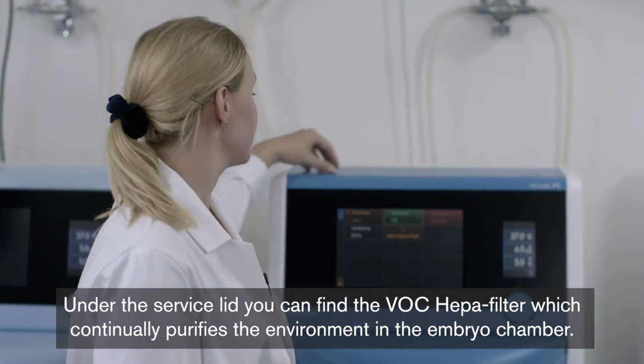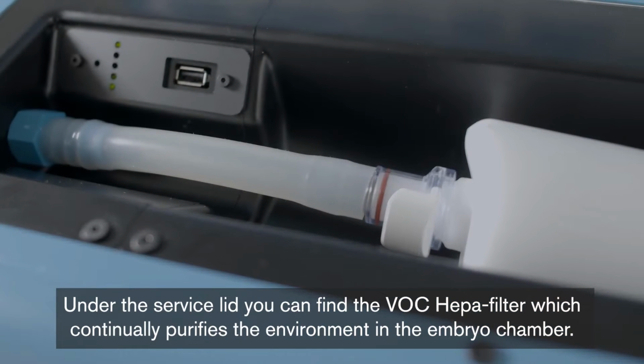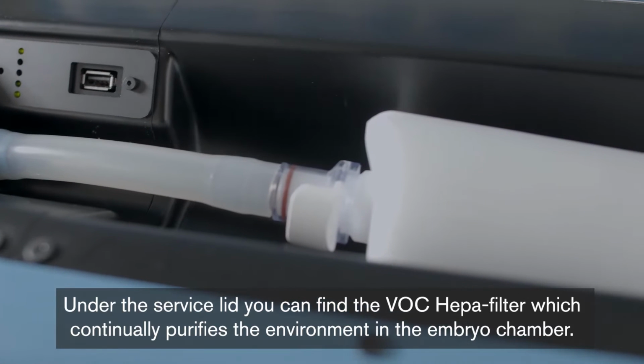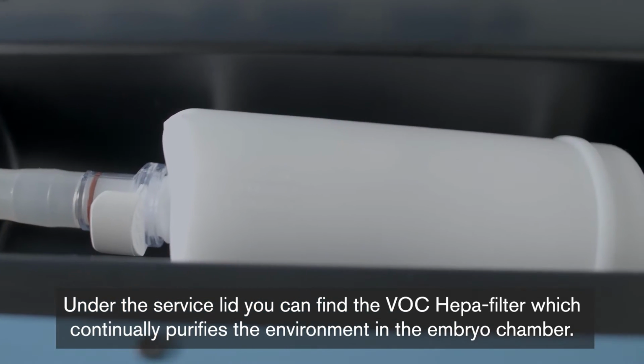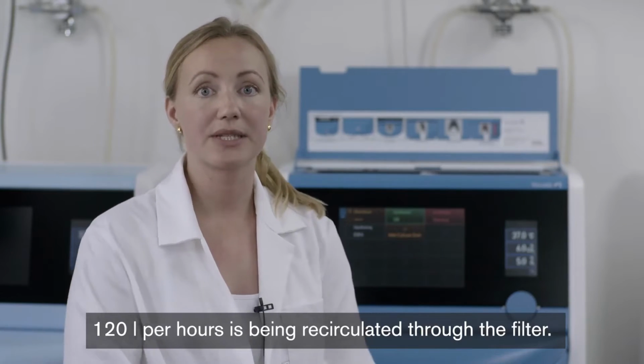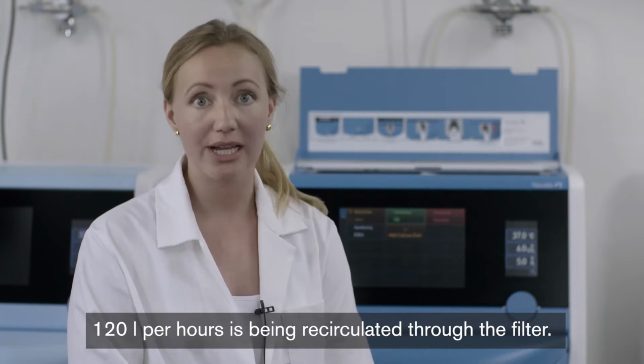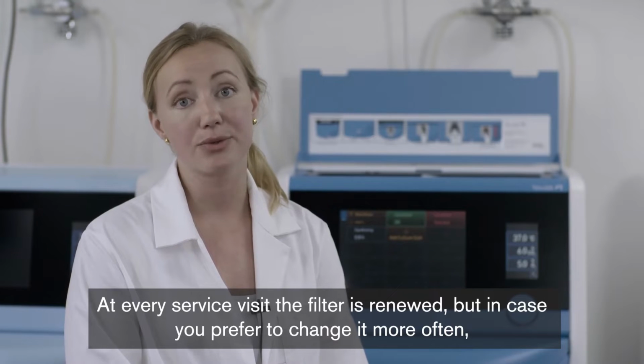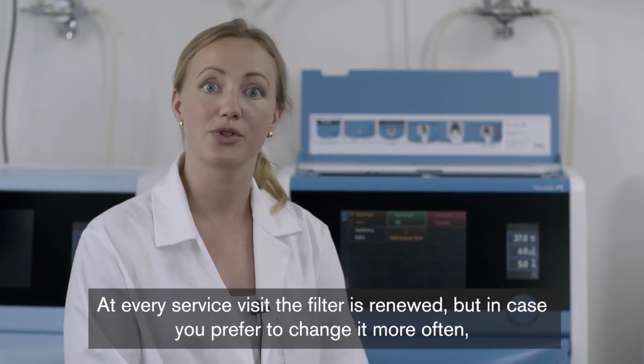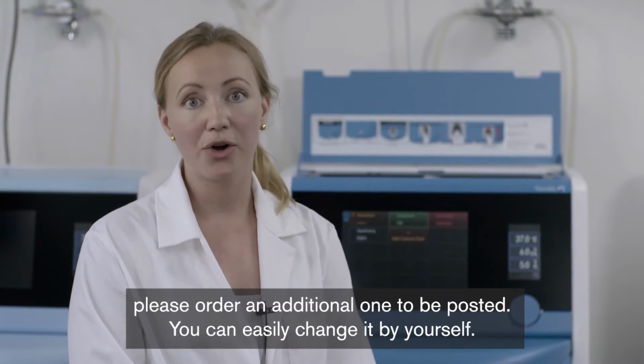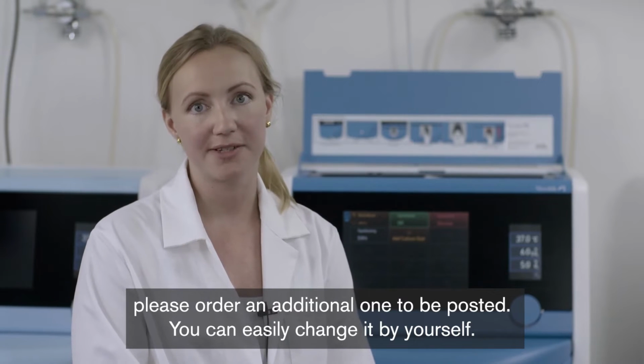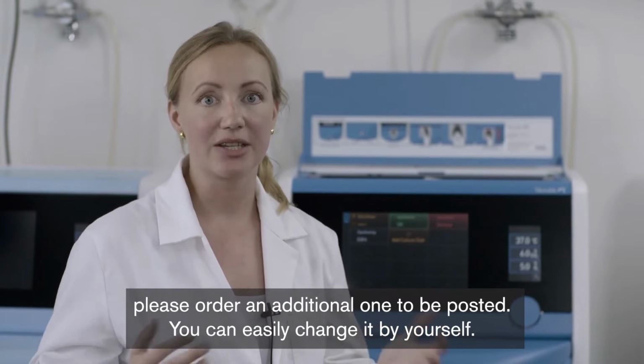Under the service lid, you can find the VOC HEPA filter, which continually purifies the environment in the embryo chamber. 120 liters per hour is being recirculated through the filter. At every service visit, the filter is renewed, but in case you prefer to change it more often, please order an additional one to be posted. You can easily change it by yourself.